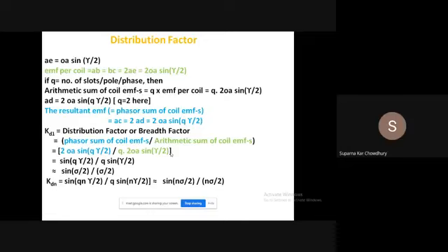And among the odd harmonics, third and multiple of third or triplet frequency harmonics, that is taken care of by the star delta connection itself. So we are not interested in that. What we are interested in is fifth, seventh, then 11th, and so on. Fifth and seventh is the most important because magnitudes will be larger. As we go for higher orders, the magnitude decreases.